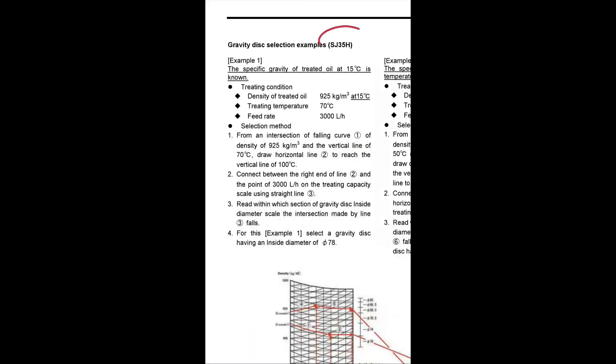We are going to take the SJ35H purifier model for plotting the nomogram now. Taking Case 1: we know the specific gravity of the treated oil at 15 degree centigrade. We get this 15°C specific gravity either from the bunker delivery note during bunkering, or from the fuel oil analysis report after bunkering when we send a sample to the laboratory. So let's suppose we get 925 kg per meter cube at 15 degree centigrade. We are going to treat this oil at 70 degree centigrade keeping the feed rate at 3000 liters per hour. These are our treating conditions, and now we are going to plot the nomogram and select the appropriate gravity disk.